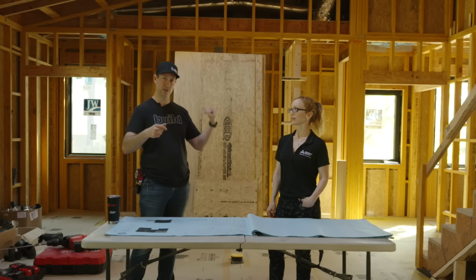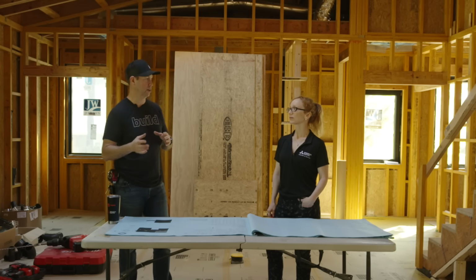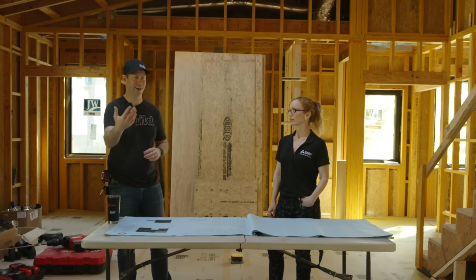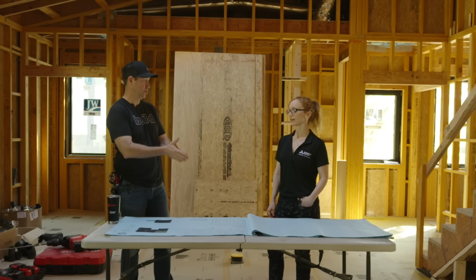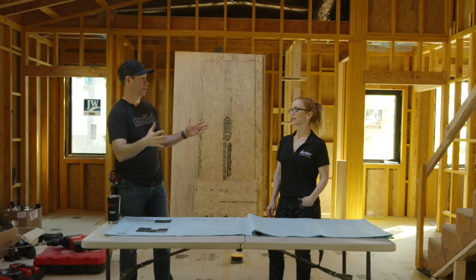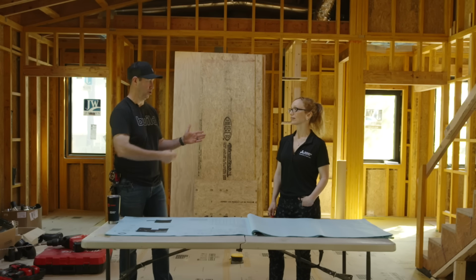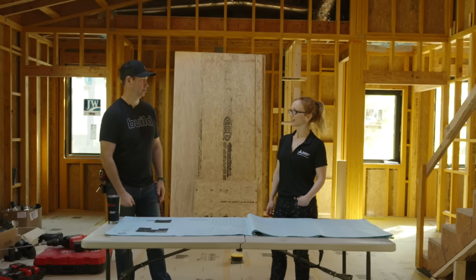That 4-ton system that I have outside, 1% of the year it's 100 degrees outside. Most of the time it's 70, 75, 80 degrees out. It's not 100. So when I need 4 tons is by design on this Manual J, 1% of the hours of the year. When I need it, I've got it. But most of the time I can throttle that back and use less power, less amperage to drive that compressor. Did I say that correctly? Exactly right. That's exactly right.